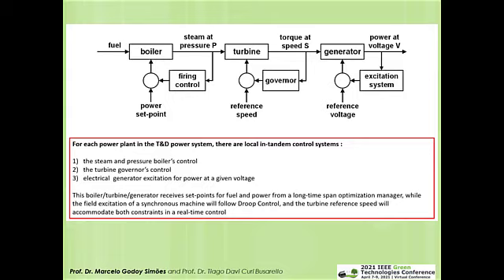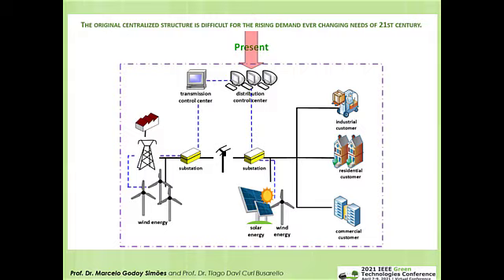The same principles can be applied to hydropower plants. If an induction machine is used instead of a synchronous machine, D and Q transformation will allow the machine to match the operating torque and angular speed to supply power. But such a control system is dynamic and a little more complicated than in synchronous machines. Synchronous generators are usually the choice for multi-megawatt installations, while induction machines are used for kilowatts to around a few megawatts, mostly in distributed generation based systems.